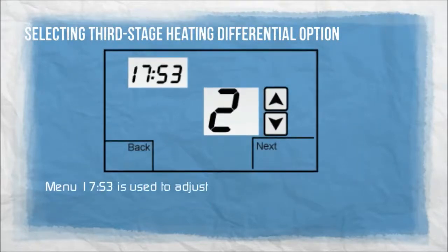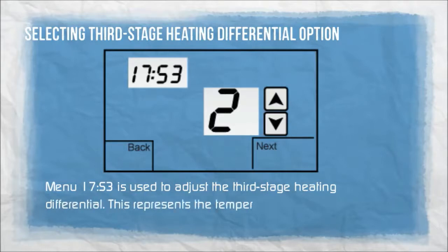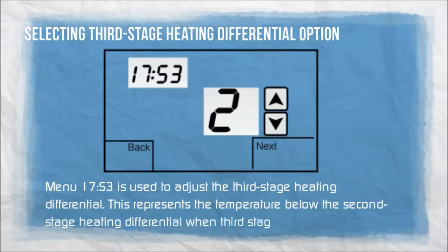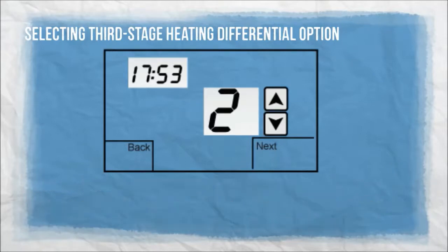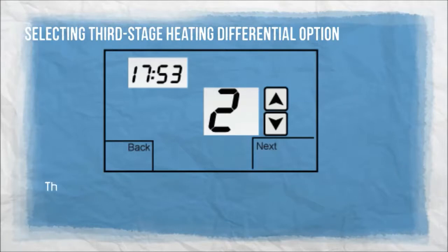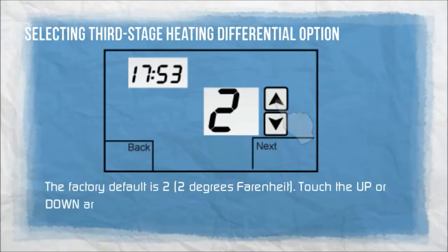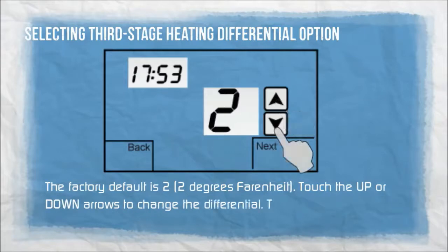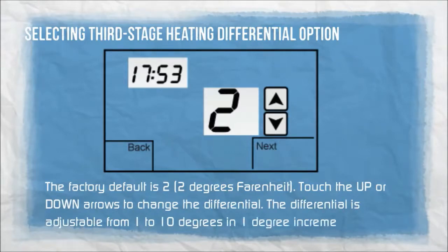Menu 17S3 is used to adjust the third stage heating differential. This represents the temperature below the second stage heating differential when third stage heat is energized. There is a three-minute time delay before third stage heat is energized. The factory default is two degrees Fahrenheit. The differential is adjustable from one to ten degrees in one degree increments.